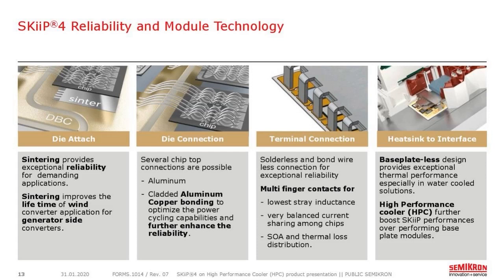Especially this layer needs to survive the low frequency, high temperature swing during low frequency operation of, for example, a generator side converter. So the sintered connection is one essential ingredient in order to reach the reliability typically necessary for a long-lasting operation of 20 or more years for a wind turbine.